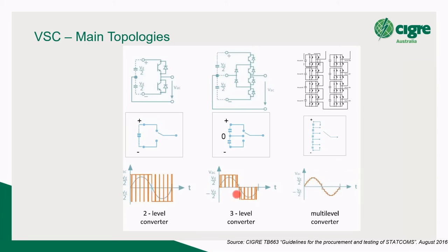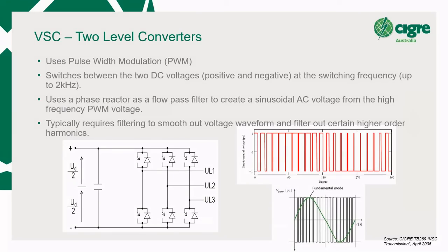Now, just going through each one, the two level uses pulse width modulation, and it basically switches between positive and negative, positive and negative. In the case of direct link, it's 80 kV positive, 80 kV negative. So it's got this switching band of 160 kV switching, bang, bang, bang, bang, 2000 times per second. You can imagine the type of heat that's generating. It's equivalent to when you're operating your computer and all your power electronics has been working pretty hard. You feel that heat being generated from the switching. Imagine that, but each switch is 2 kV. So that's pretty much a two level.